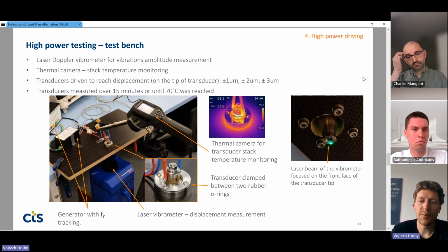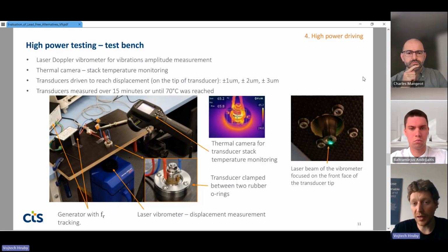If we proceed to high power testing, we prepared a test bench to test transducers at high driving levels. This test bench consisted of a laser Doppler vibrometer, which we used to measure vibration amplitude at the tip of the transducer. Then we incorporated a thermal camera to monitor the transducer stack temperature. And we drove transducers at resonance frequency to reach specific displacements.